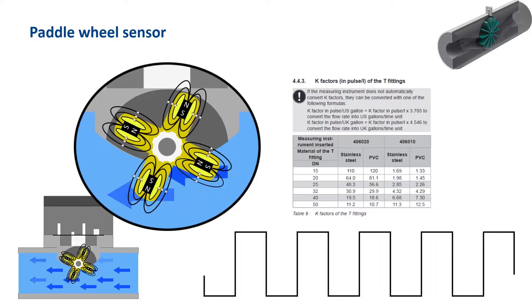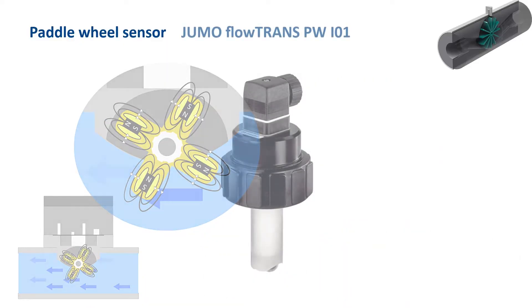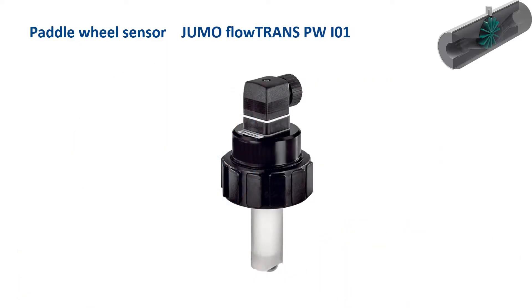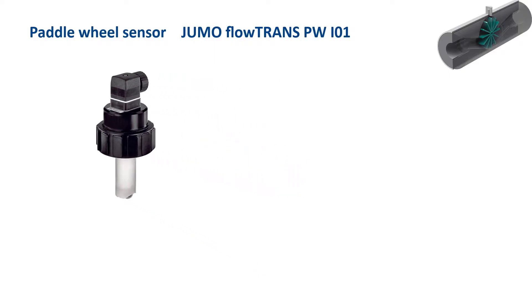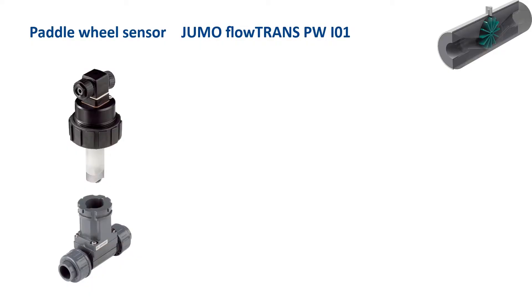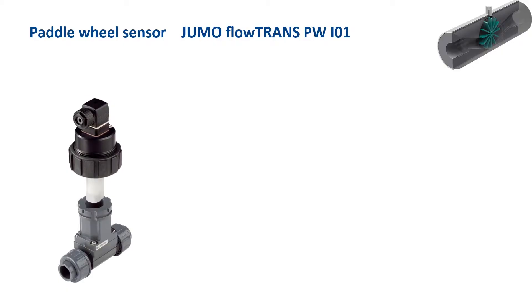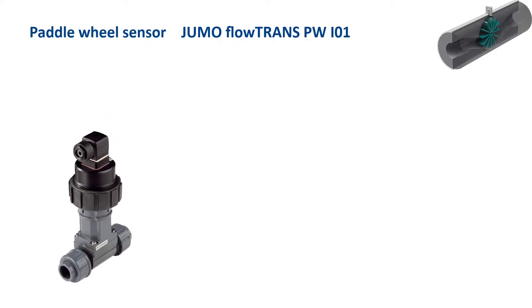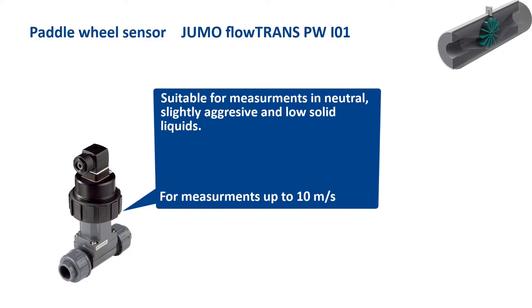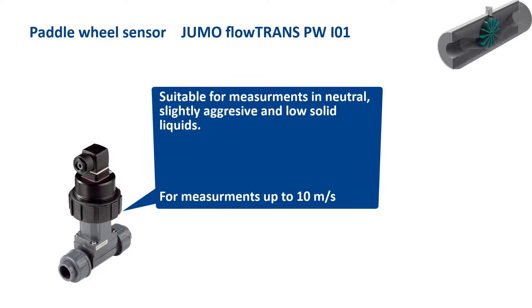The k-factor is related to the pipe cross-section and is specified by the manufacturer in the datasheet. At Jumo, the paddle wheel sensor is called FlowTrans PW. This is a plug-in paddle wheel sensor fastened to the respective process connection — T-pieces, pipe clamps, or welding spigots — by means of a union nut. This allows for quick in-process insertion or replacement, making installation and maintenance easier. It is suitable for flow measurement in neutral, slightly aggressive and low solid media and can measure flow velocities up to 10 meters per second.